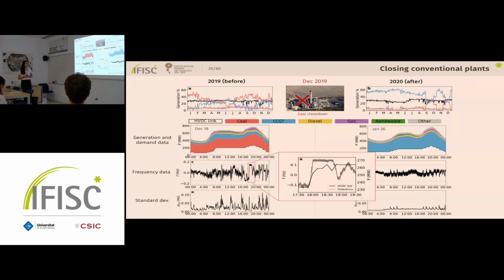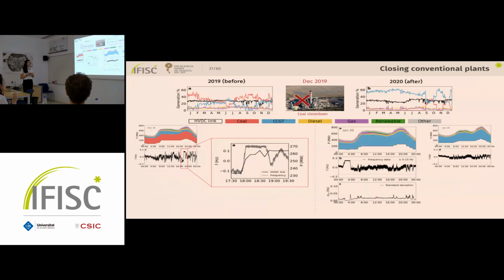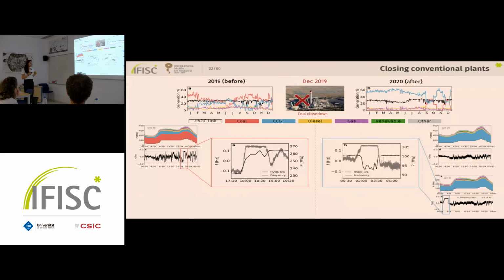Moreover, we also noticed that in some cases, the frequency was staying fixed at the 0.15 Hz value for quite some time. And this was quite surprising to us because we did not expect this from the typical control mechanisms of power plants. And this was happening not only before the close down, but also after, as you can see here. And we noticed that when that is the case, the power of the link fluctuates a lot, as you can see here. The link has a rather constant profile. It has these very large step changes, but otherwise it's very constant. But during these moments, it fluctuates a lot. And so we concluded that the link is responsible for keeping the frequency there.